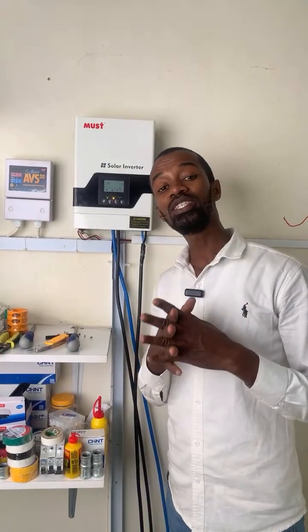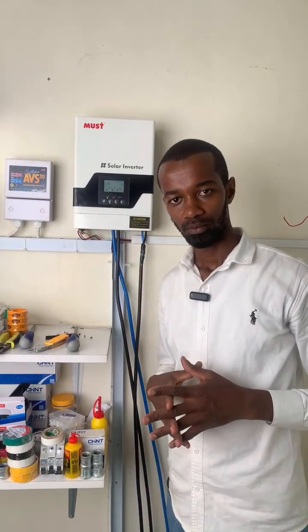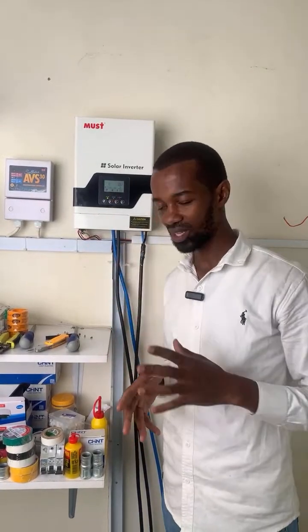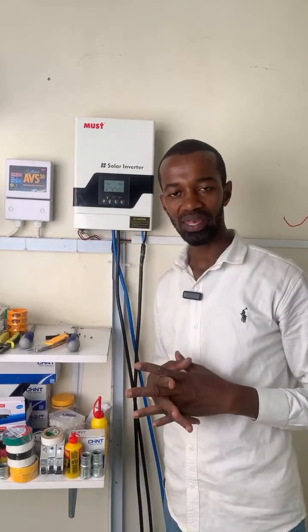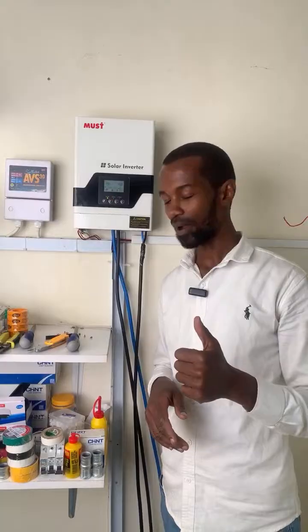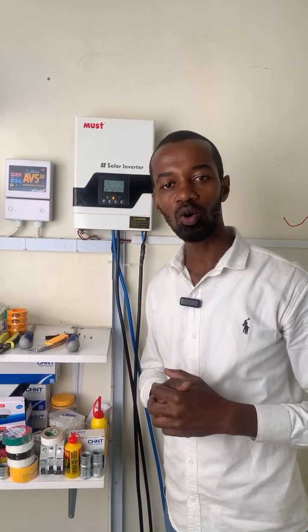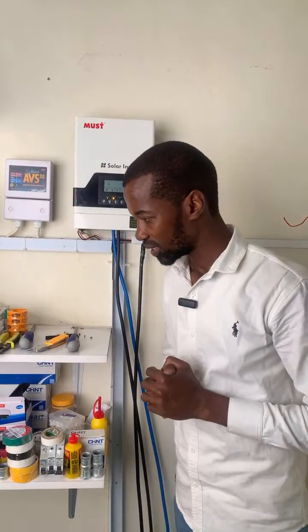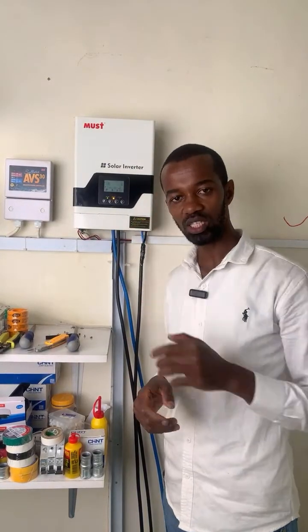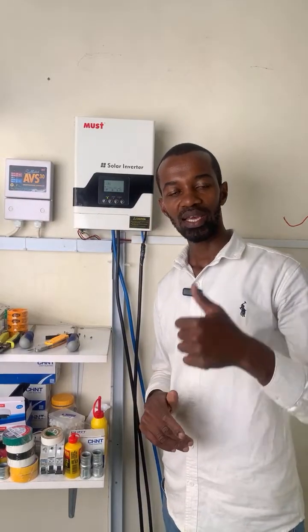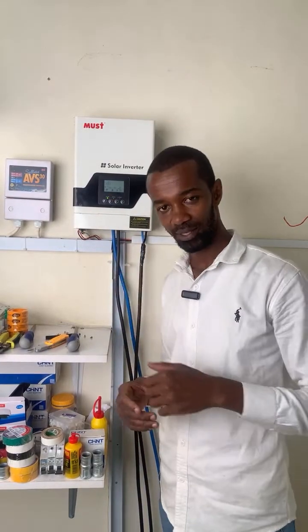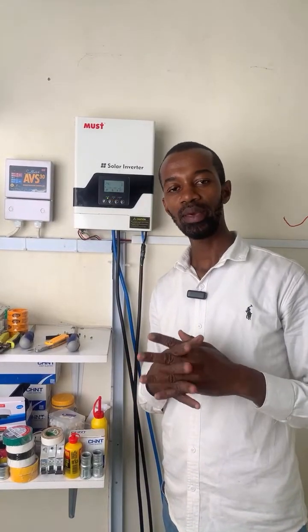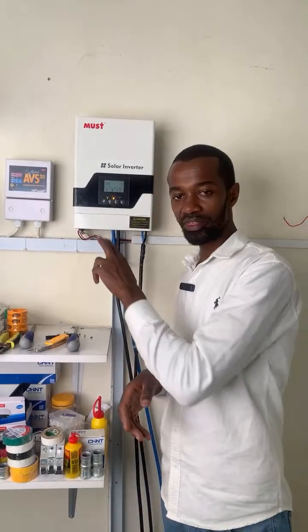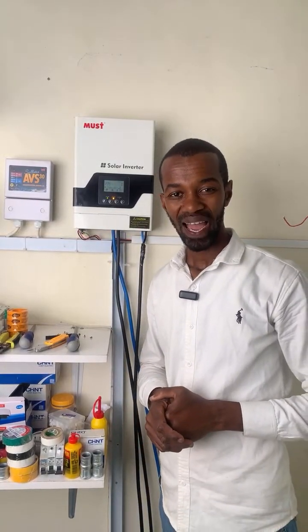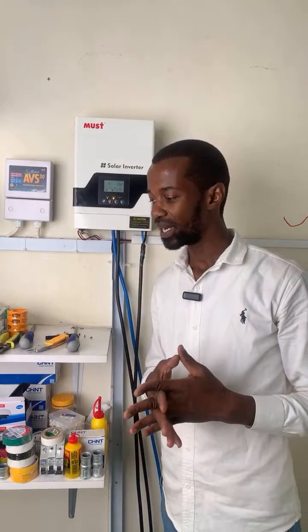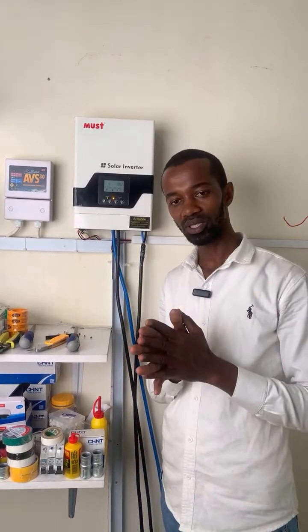Now, when it comes to disconnecting the entire system, maybe you want to transfer it, shut everything down, or repair the inverter, the first procedure is: if you have PV, shut down the solar connection first. Another important thing, disconnect the AC that is feeding the inverter, so that you are only remaining with the battery. Then disconnect the load, and finally the battery will be last. So it is like the opposite.